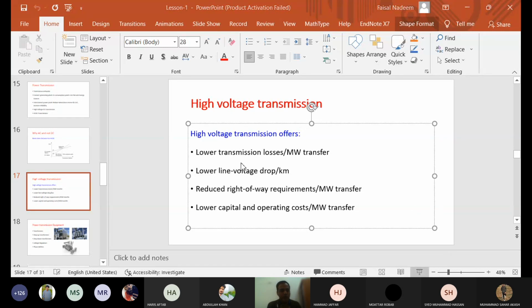High voltage transmission offers lower transmission losses. Why will losses become less? Because we have high voltage. You know that power P is equal to V times I. If we want to transmit the same amount of power, we fix the value of P, and if we increase the voltage, we have to reduce the value of the current. So if the voltage is high, if we increase the voltage, automatically the current will reduce. And if the current reduces, then the I-squared-R losses will reduce.